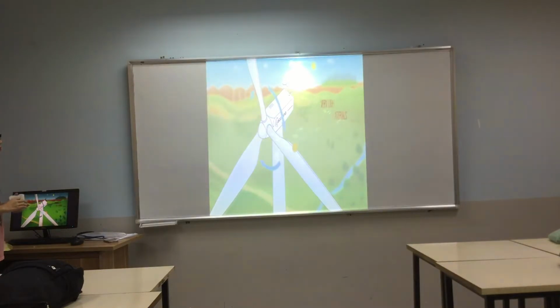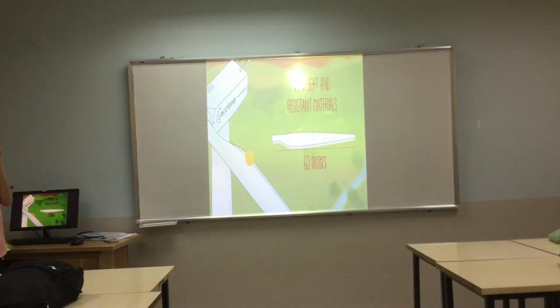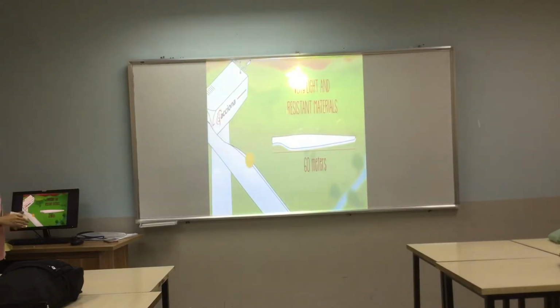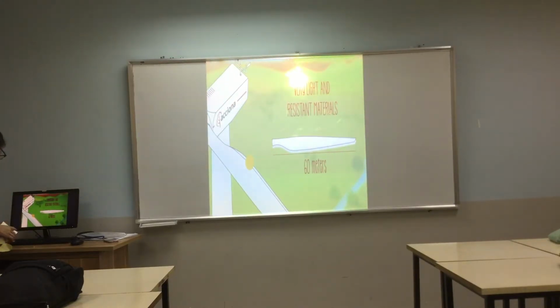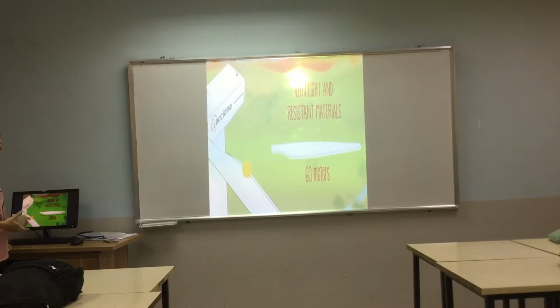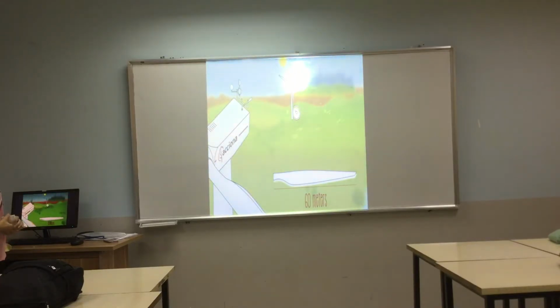They can be as long as 60 meters each and are made of very light and resistant materials that ease movement. This is why they can produce energy even with very light winds, starting from about 11 kilometers per hour. With very strong winds, above 90 kilometers per hour, the blades are placed in the feathered position and the turbine stops spinning for safety reasons.